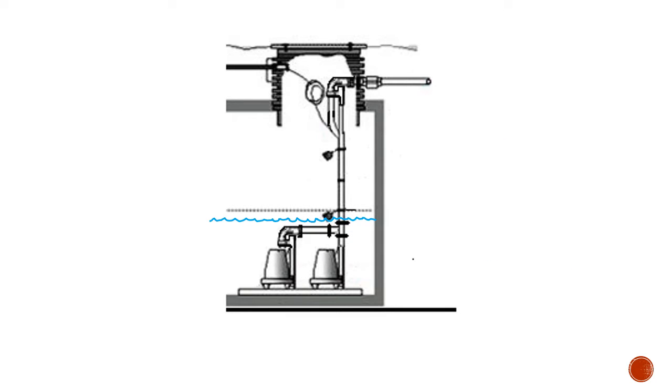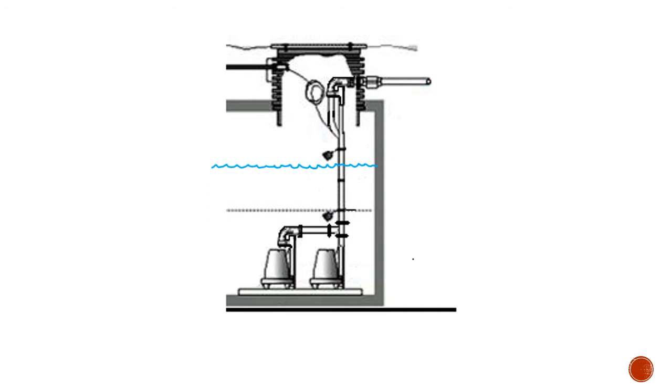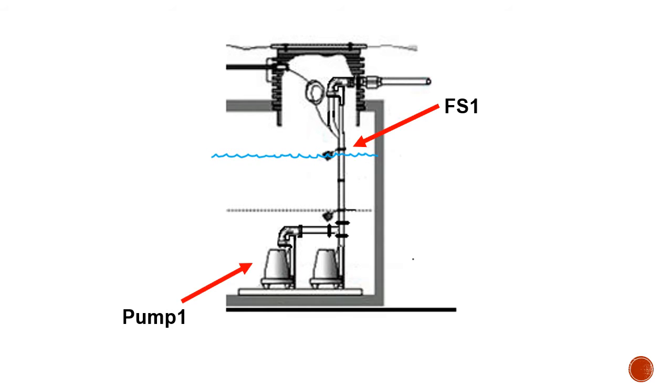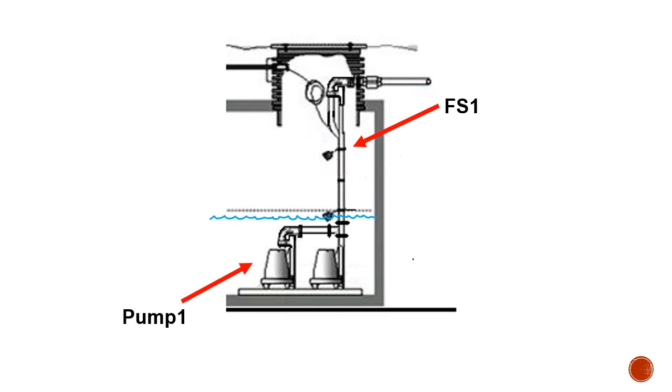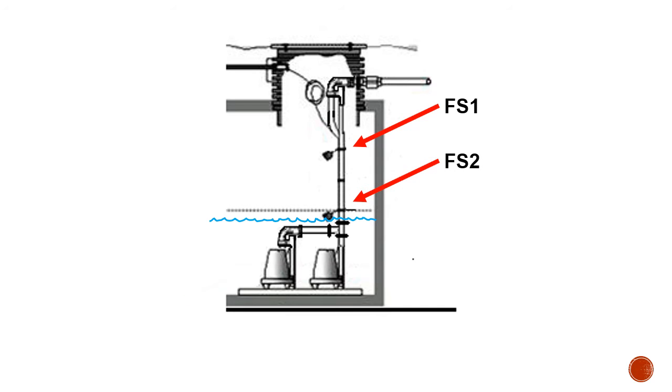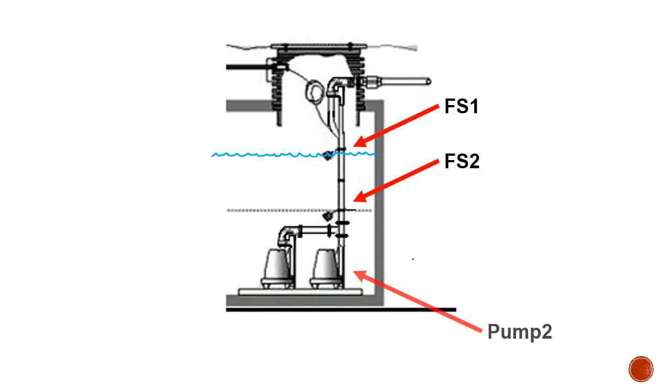So what I have here is I have two lift pumps down at the bottom and a couple of float switches. Now my float switches are going to start and stop my pumps. So as my water level goes up it'll trigger float switch one which will turn on one pump. Then as the water level goes down my other float switch will turn that pump off.